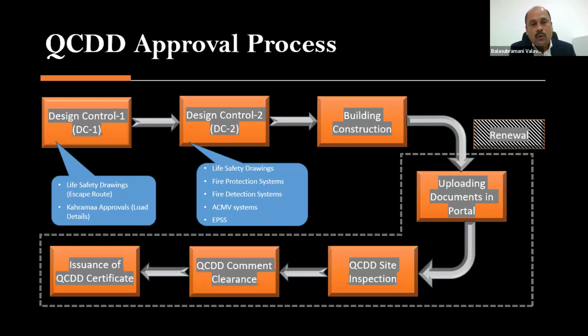Upon approval, you have to start the construction work, starting from excavation, making the building, placing all the equipment, where you have to perform the testing and commissioning of all the equipment, not only related to firefighting. Whatever has been approved, you have to make it. Upon completion of that, you have to submit your as-built drawing with the relevant documents. You have to upload those documents in the portal. The moment you upload in the portal, it will be reviewed and verified by the QCDD personnel, and they will give you the date. They will come for an inspection and do the inspection at site level.